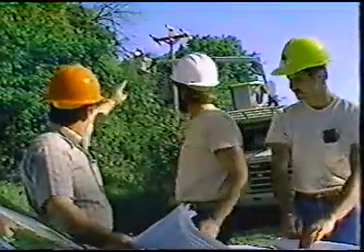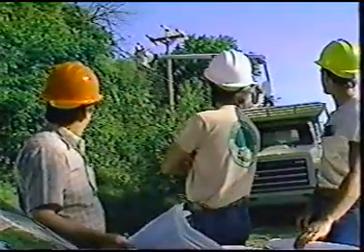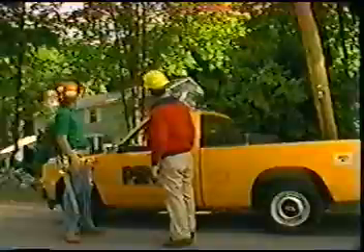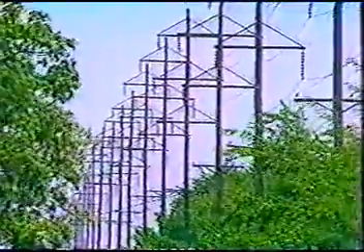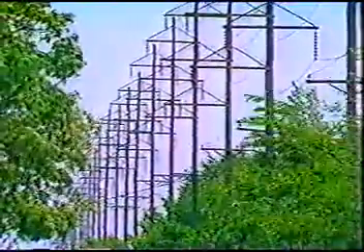You must be aware of the maximum nominal voltage of a system because of the greater ability of higher voltages to overcome a given resistance. This will govern how close you can actually come to an energized line. Key indicators, however, are the size and number of insulators. Remember, the higher the voltage, the larger and more numerous the insulators.